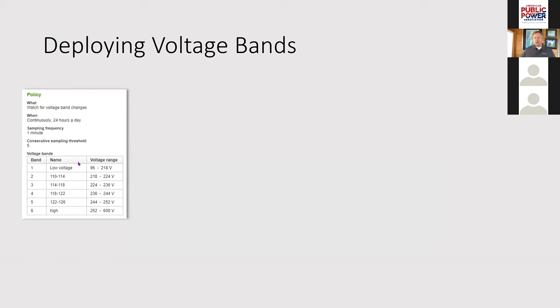For example, at this particular meter, a snapshot over time shows at these particular times this meter crossed a threshold from 5 to 4. It suggested it crossed from a range of 122 to 126 into 118 to 122. So 122 became a tripwire that sets off this event, which is sent upstream to OATI. Now I have some idea, as I lower the voltage at the substation, how well or not well the voltages are responding at the meters out in the field.